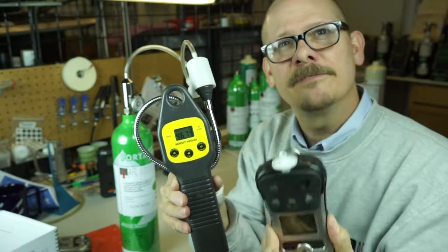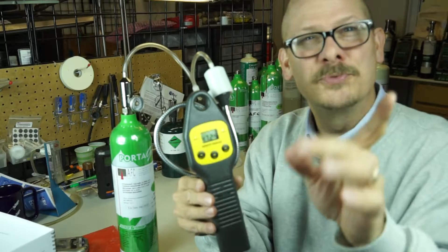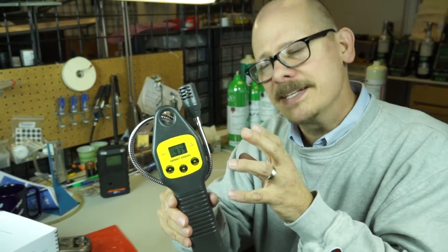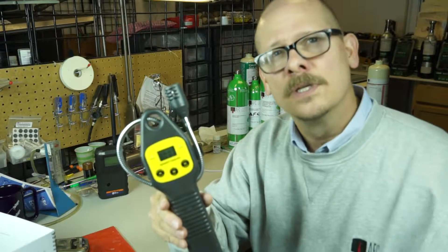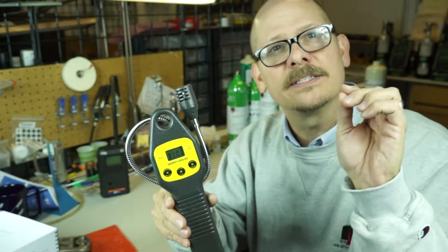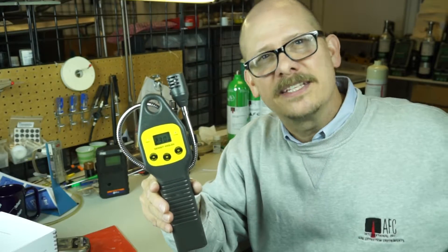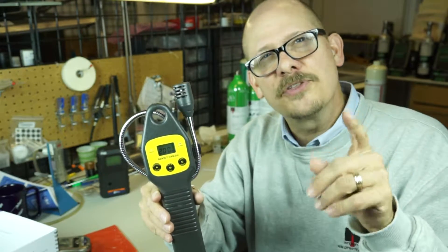But from a low-end perspective, the Q-RAE 3 or any multi-gas instrument for confined space or LEL work is really not appropriate for the low-end detection limits of leak detection. Shutting the gas off — as it comes back down it goes back into parts per million and then all the way back down to zero. So what I've shown you here is low-end detection limits, instruments designed for low-end light hydrocarbons and fuels, and sensor response and recovery. It doesn't immediately give you an answer — all instruments take time to respond, and the recovery phase can also take a little time.